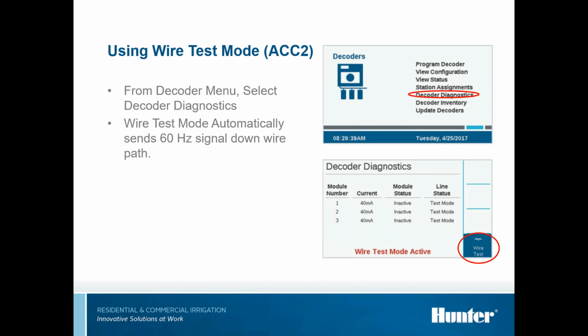Now on the ACC2 controller, if you go to the decoder menu and then select decoder diagnostics, it takes you to the screen down below. At that point, if you look in the bottom right, it has wire test. If you activate the wire test mode, it will take it from DC and go to 24 volt down the line without having to disconnect. So that's another great feature that is built into the ACC2 controller, or A2C.